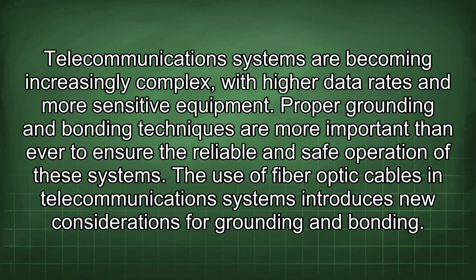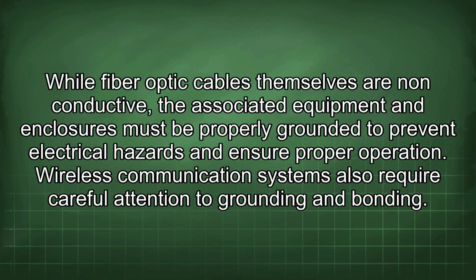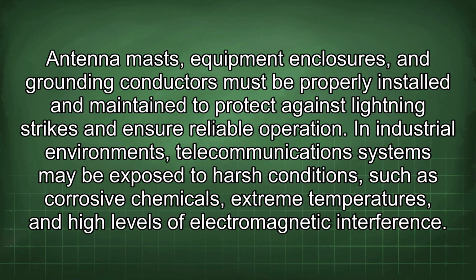The use of fiber optic cables in telecommunications systems introduces new considerations for grounding and bonding. While fiber optic cables themselves are non-conductive, the associated equipment and enclosures must be properly grounded to prevent electrical hazards and ensure proper operation. Wireless communication systems also require careful attention to grounding and bonding. Antenna masts, equipment enclosures, and grounding conductors must be properly installed and maintained to protect against lightning strikes and ensure reliable operation. In industrial environments, telecommunication systems may be exposed to harsh conditions such as corrosive chemicals, extreme temperatures, and high levels of electromagnetic interference.